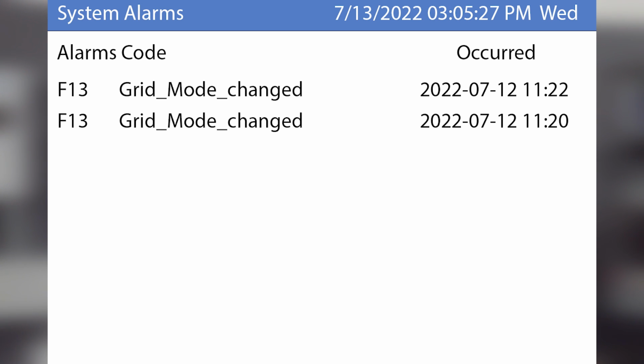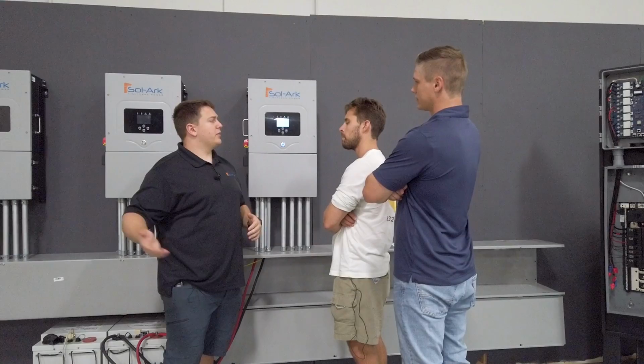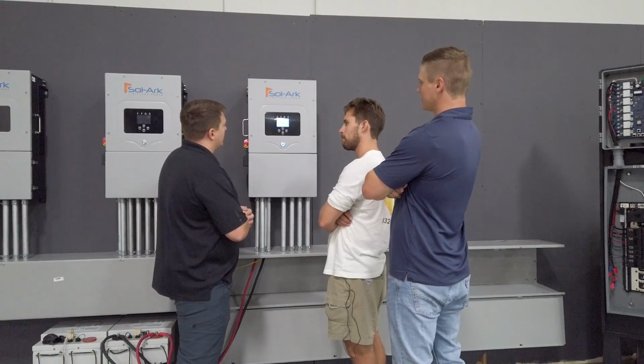For instance, there are a few F13s on here—that just means we changed the grid mode. So if you go from 120/240 to 208 mode, you'll get an F13. Looks like an alarm, but it's really just a notification. There's also a couple others like parallel system stop—a lot of times that just means someone turned off one of the other units, and this one's saying, hey, I can't talk to my other friends here in parallel. So it's really just a notification.